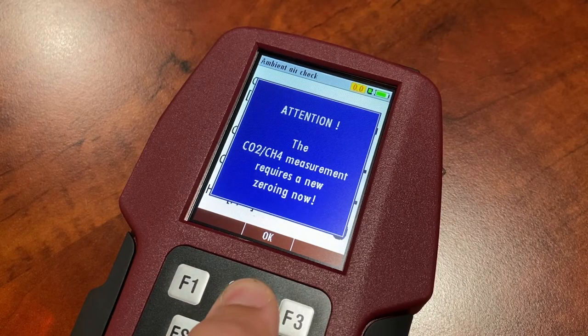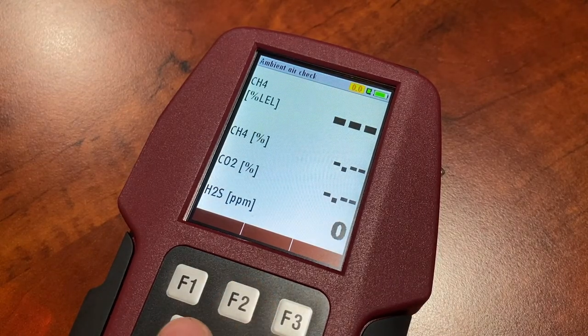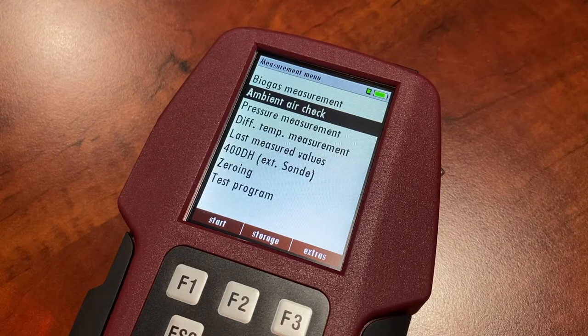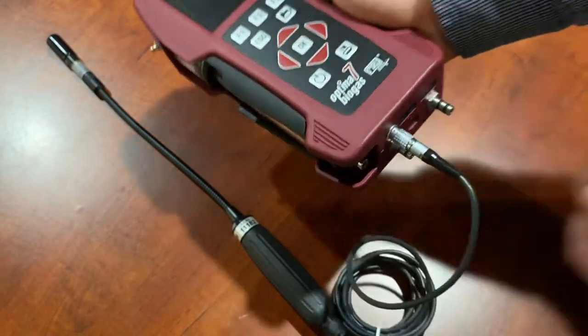In all seriousness, the Optima 7 that comes with the landfill kit is pre-equipped with sensors for oxygen, hydrogen sulfide, methane, and carbon dioxide, as well as a biogas pressure sensor and a universal auxiliary port.